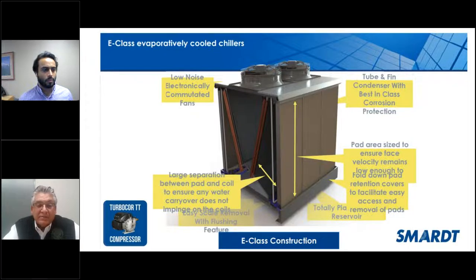This is quite unique. Some of us who've been around a while remember a lot of manufacturers in the past adding evaporative pre-cooling to their condensers, either in a packaged rooftop or other type products, to help with the condensing temperature. We can do that as standard on our air-cooled machines by using a media. Essentially, it's an evaporative cool type media that has a pump assembly, a sump, and the water runs over the media as the air passes through the media, then goes through the condenser coil. It provides some additional efficiency and also the ability to get a little more capacity out of the machine at higher head pressures. It's a very economical way of providing higher capacity at elevated temperatures as well, especially in more dry arid areas, like other parts of Oregon and Washington State, or desert areas, right?